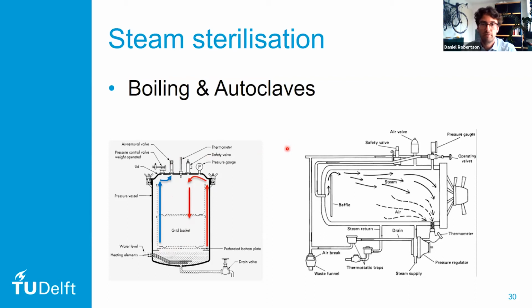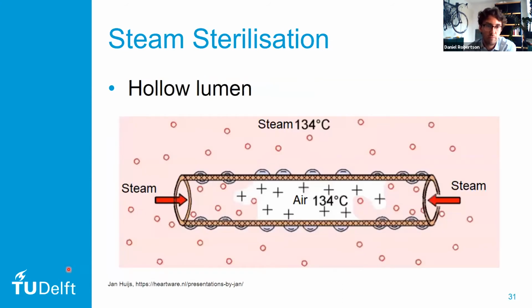Now, the other type of autoclave that we have is the horizontal one. These horizontal autoclaves often have a vacuum before the sterilization starts. What the vacuum does is, instead of, like in a vertical autoclave, the remaining air in the autoclave being pushed out, the vacuum sucks out the air and replaces all of the air in the autoclave by steam. Now, this vacuum is very important in sterilizing laparoscopic instruments because in laparoscopic instruments we have a very long hollow lumen.